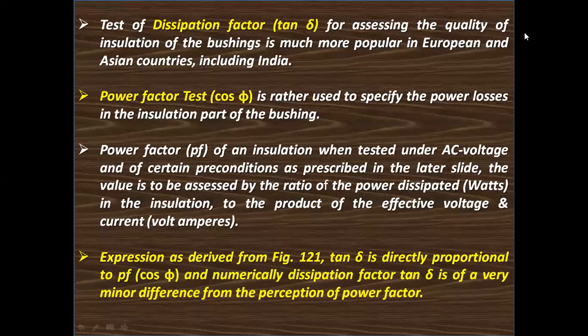As derived from figure 121, tan delta is directly proportional to power factor cos phi, and numerically dissipation factor tan delta is of a very minor difference from the power factor. Actually, the power factor test is popular mainly in USA and Canada.